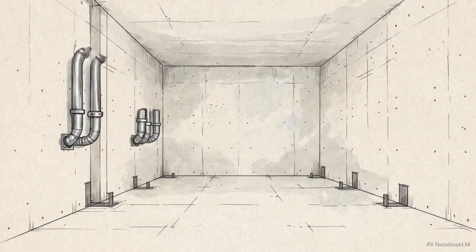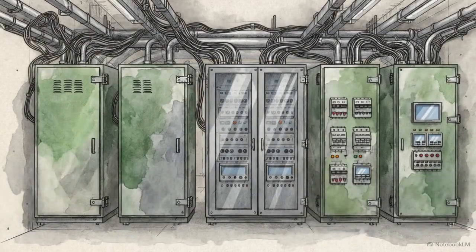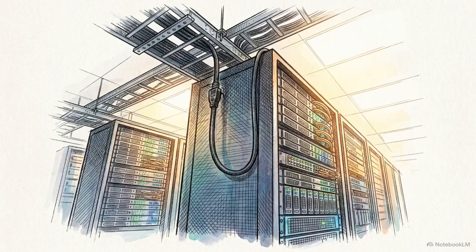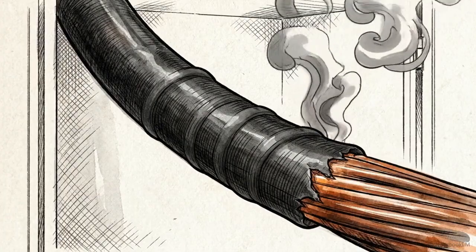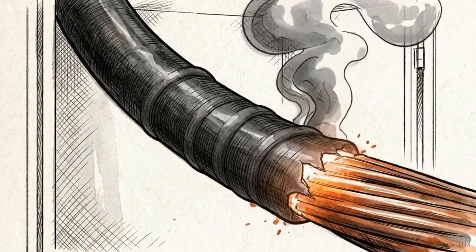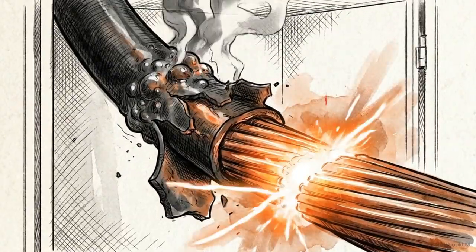Achieving a continuous 99.999% uptime requires stripping away luck and replacing it with rigorous mathematical sizing and engineered redundancy. We begin building our model at the very end of the power path, the physical connection between the PDU and the server rack, to determine required capacity. Sizing this infrastructure incorrectly by even a small margin leads to overloaded circuits, cracked breakers, and physically melted copper cables.